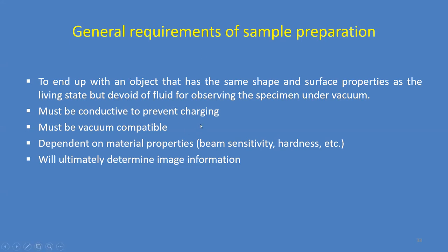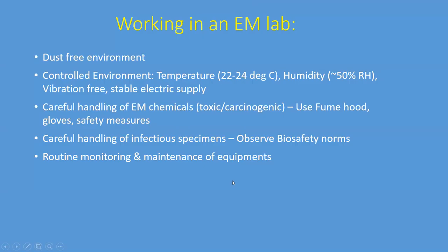It must be conductive, so you can't have static charging there, and it must be vacuum compatible. And results also depend on material properties, like beam sensitivity, hardness, softness of the material. All these things will finally determine the image quality. So typically working in an EM lab, this goes for both TEM and SEM, you need a dust-free environment, a very controlled environment, temperature, humidity, stable electric supply, vibration free. Okay, these are things that have to be kept in mind before installing an equipment.